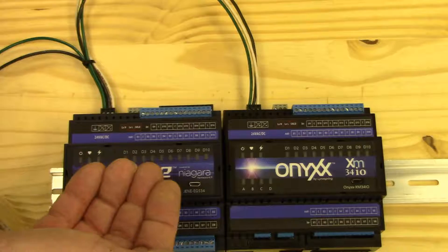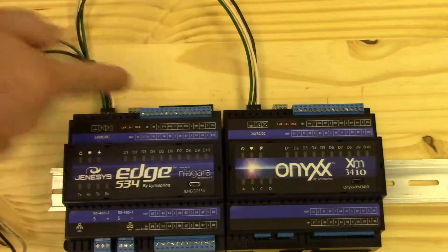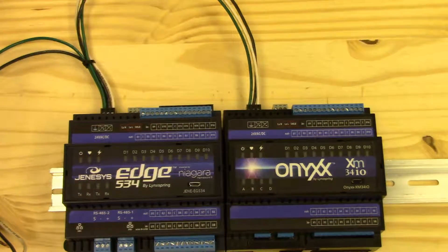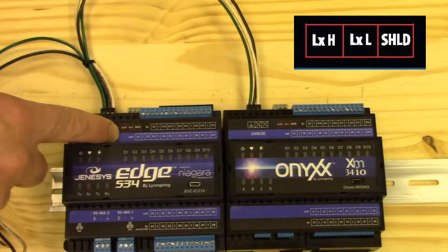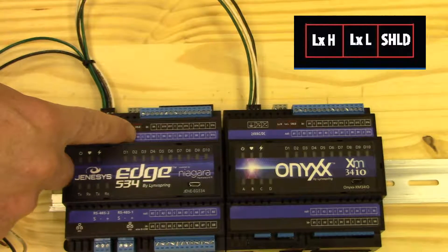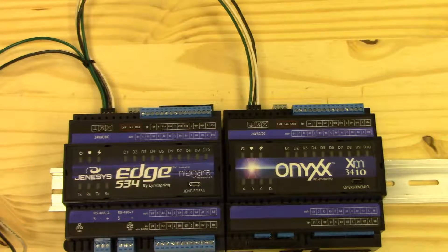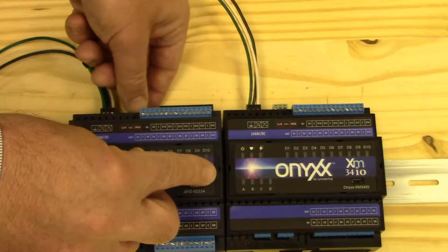To get the Edge 534 to communicate with the Onyx XM, we use these blue terminals — that is our Onyx network. The Onyx network is indicated on the label by LXH, LXL, and Shield. It's polarity-sensitive, and I've pre-wired a cable to do exactly what we need to do.